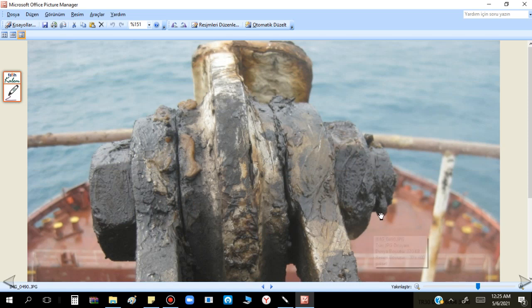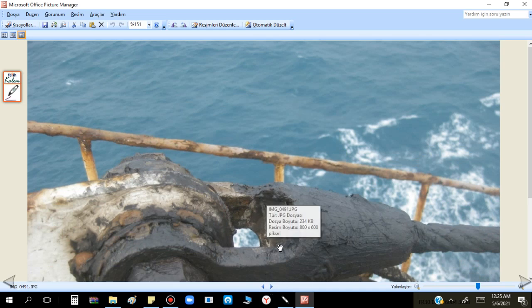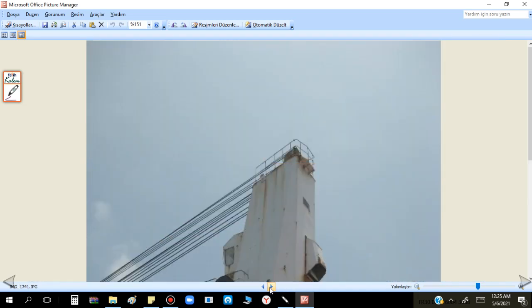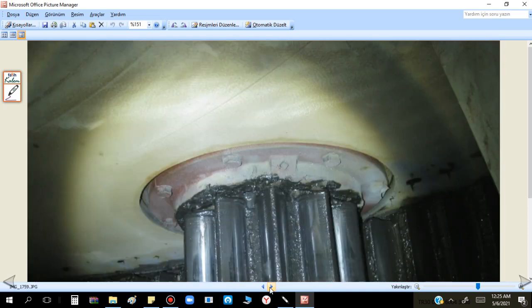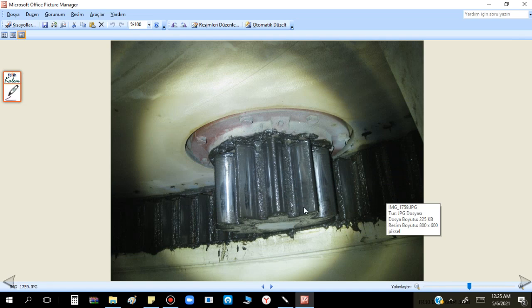This is the socket. You see the cotter pin is complete - this is very important. When you go, you just make a visual check: any crack, any deformation. Crane house number one, so we enter inside. This is the slewing motor I explained - it makes the voice when swinging, turning this gear.